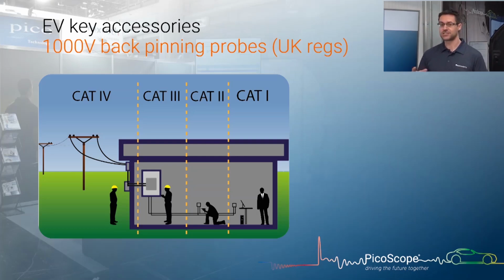The reason is that if you attach a probe that's of a lower Cat rating, you automatically derate the whole thing. So in our guided tests, when we talk about using the diff probe, especially for the charging communication stuff, which technically is on the low voltage side, you could argue you could just use a x1 test lead in that situation. Not really, because you're connected to the mains, so automatically you come underneath the Cat ratings.